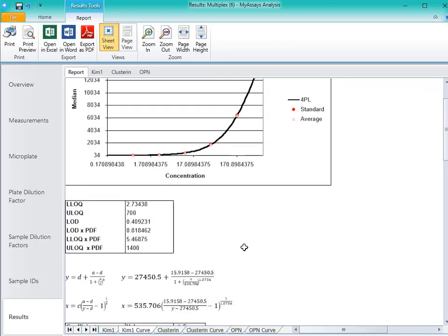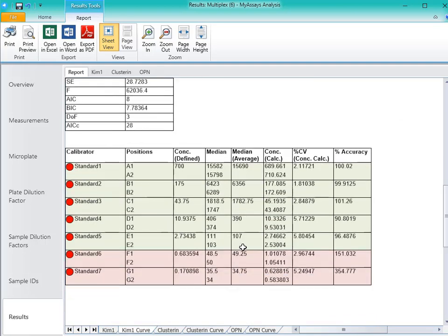we can view the fit details, including the calibrator table. This table contains the data surrounding your standards, including the calibrator name, position, defined concentration, median values, average median values, calculated concentration, the percent CV between replicates, and the percent accuracy. The standards that meet our accuracy and precision thresholds are highlighted in olive, and those that don't are highlighted in light red.